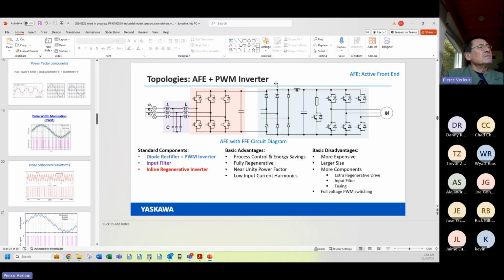In this active front end scheme, you've got capacitors here on a constant voltage DC bus. And the matrix drive doesn't have capacitors and doesn't have a DC bus. So their claim is that because we've got this capacitance-backed DC bus, capacitors are like batteries, we can maintain full voltage to the motor under more conditions than the matrix drive can. Fact: the capacity of these capacitors to supply a motor with energy when the power line is cut off is about 1 millisecond before the capacitors drain out.